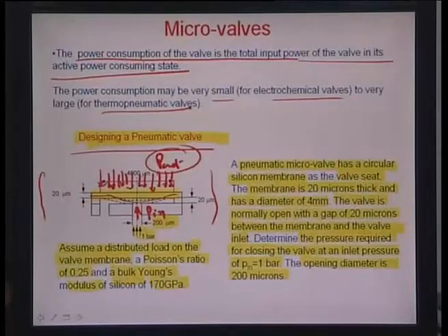This is at equilibrium, okay. This right here is an equilibrium. So, this right here again is the A open, the area of cross section which is open. So, equilibrium means that the membrane is fully seated over the inlet hole, thus valving the flow.